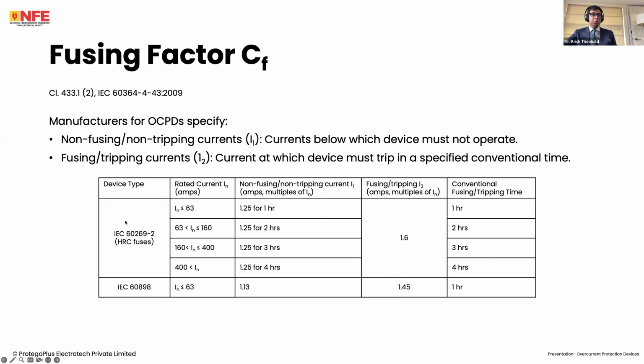So I'll just explain this again as well. So like I said, if you have a certain overcurrent protective device and the current exceeds the value of the nominal rating for an overload, the device will not immediately trip. So for example, for a 10 amp device, if you have 11 amps flow through, in most cases, the device will not trip at all. So there are two values, non-fusing or non-tripping and fusing or tripping.